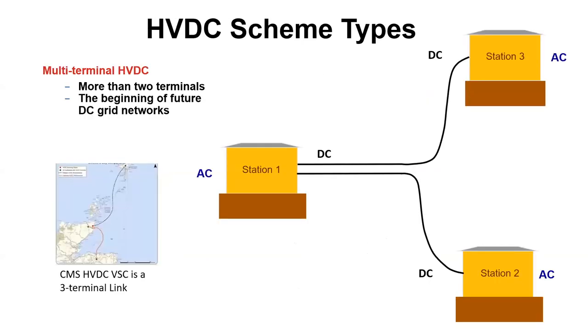The next configuration is the multi-terminal configuration, which has two or more converters connected together with different or the same transmission circuit. So the connection between station one and station three could be a cable or a line, whereas station one and station two could have a different transmission circuit. This configuration is still considered within industry as a fairly new type of configuration, but could be the beginning of DC grid networks in the future.